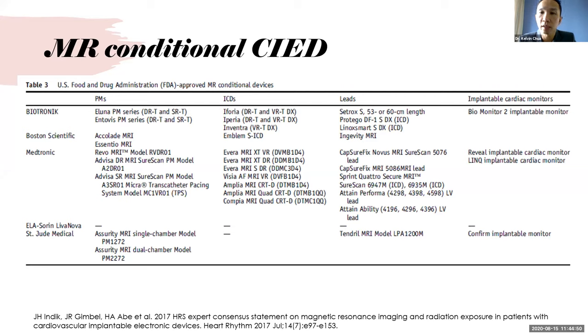For example, if you look at the Abbott and the St. Jude Medical devices, you'll see there are no high voltage devices listed here. But actually, if you check with them, they've all been made MR conditional. Their newer range of ICDs and CRTs, including those from the Quadra series, are all approved for 1.5 Tesla full body MRI. And likewise for Boston Scientific, you'll see that only the subcutaneous ICD is listed here. Actually, the newer series like Dynagen, Inogen, and Charisma are all approved for 1.5 Tesla full-body MRI as well.